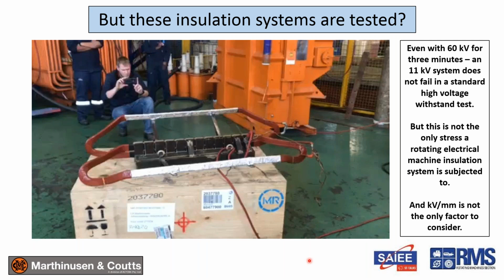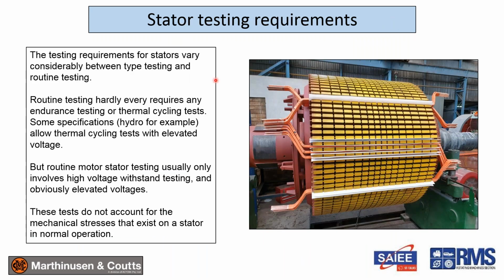And so if we look at the test requirements, there's two types of tests: routine tests and type tests. Routine testing usually is just a high voltage test. It doesn't check any mechanical integrity or thermal. It's just a voltage test. But type testing should. The most important type test, in my opinion, is the thermal cycling test at elevated voltage. So why would it not be able to detect this failure mechanism in these machines with this thinner insulation?